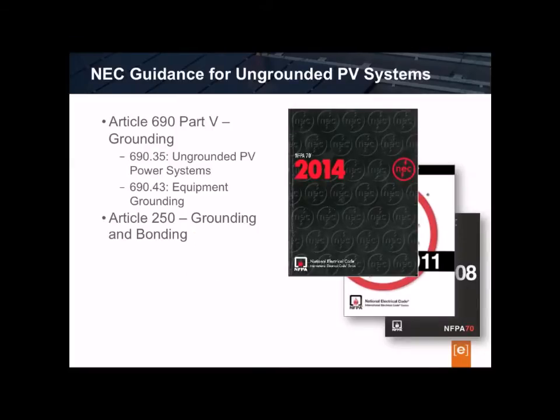These NEC requirements were developed to bring the U.S. PV industry in line with the rest of the world by adopting some of the European techniques and experiences for installing ungrounded systems, including overcurrent protection and disconnects on all circuit conductors, ground fault protection on all systems, jacketed or sheathed multi-conductor cables or raceways, additional warning labels, and inverters listed specifically for use in ungrounded arrays.